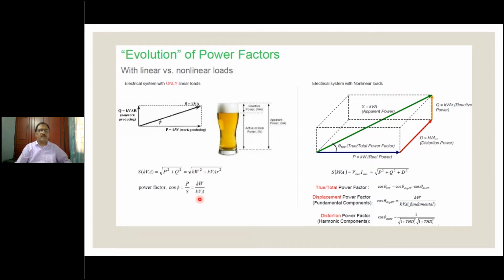It's a ratio. Now, with the advent of nonlinear loads, KVAH billing, and new understanding, we have to add one more element. Not only the active and reactive power, we also have to add distortion power. As you can see in this graph, same Pythagoras theorem, but now you have additional losses. Third element. So that third element is the distortion power. So you have reactive power caused because of the capacitor, and distortion power caused because of the harmonic. You saw how harmonic was amplified, no?